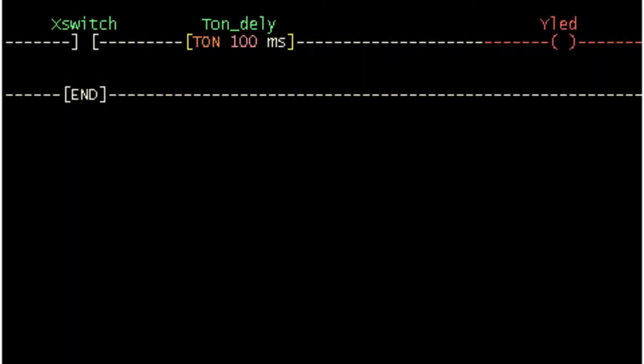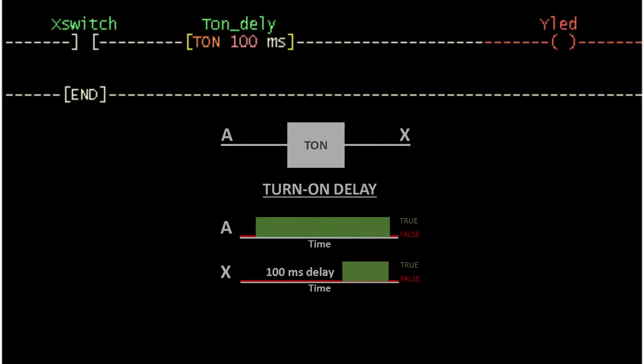The turn on delay timer can be identified by TON, the time interval, and the variable name. When the timer input signal is true for the specified time interval, its output is delayed for that time interval before it will become true. The output will immediately become false once the input changes to false. If the input goes false before the specified time interval elapses, the output will not become true.